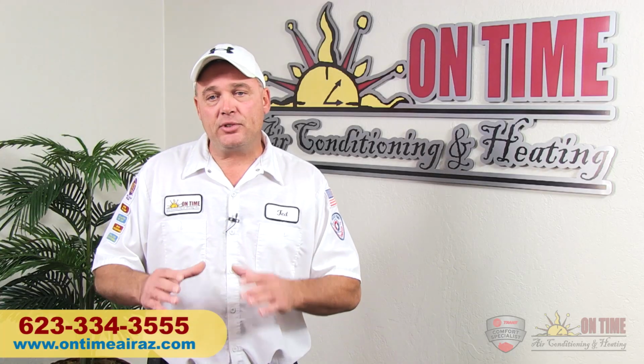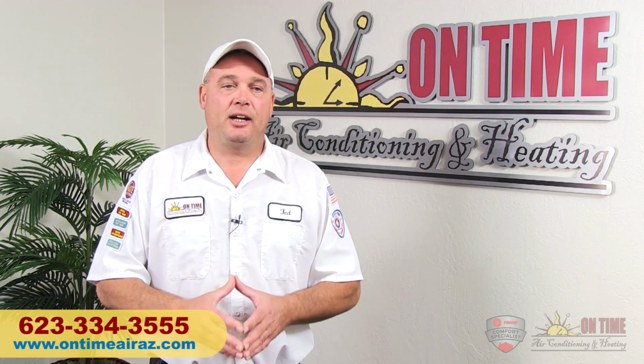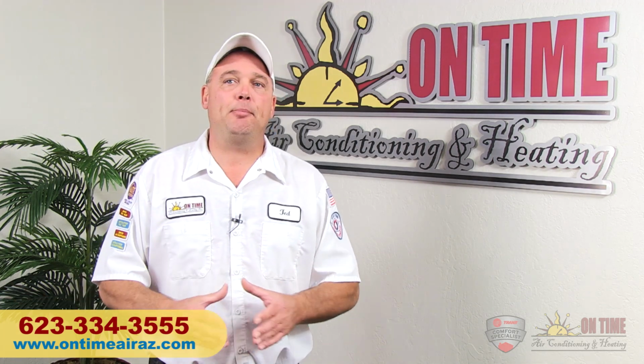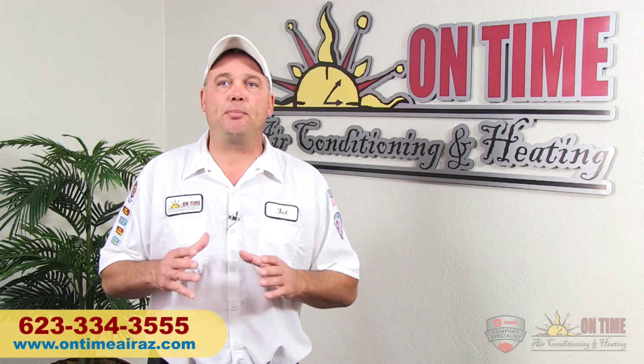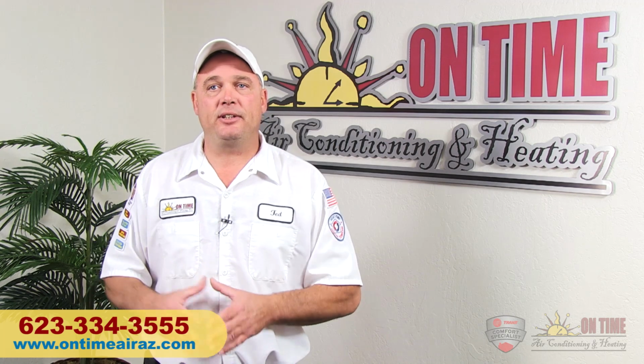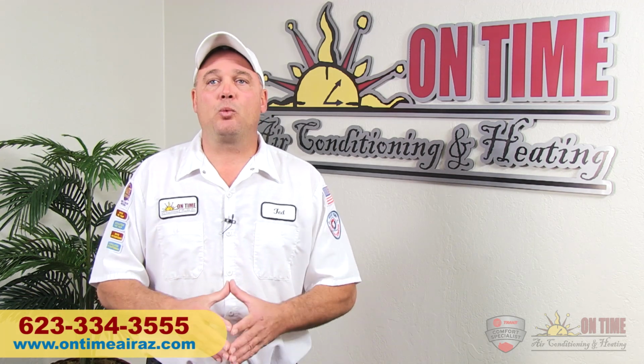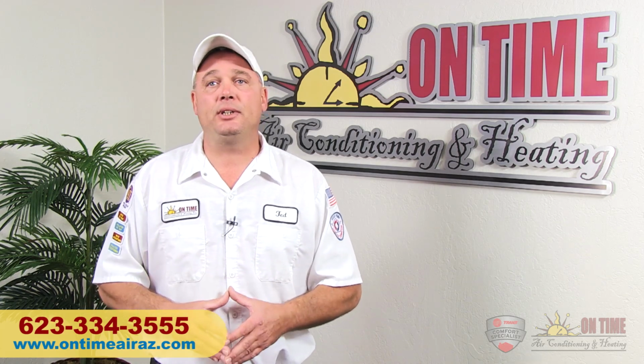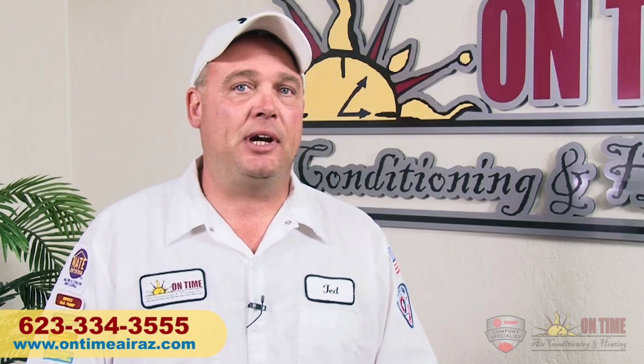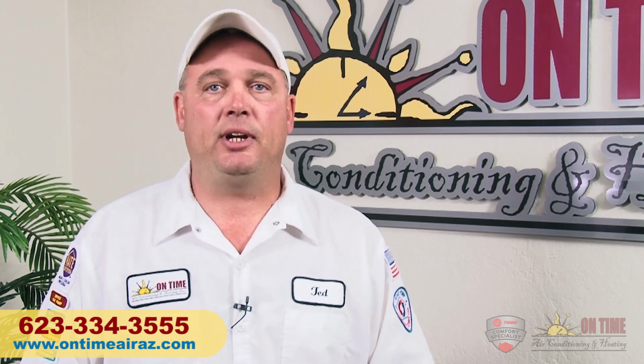So 75% of the time we come on in low gear. I dump my capacity by about 30%, so I'm only operating at about 70% of the power, 75% of the time. Because here in Phoenix, we size our units for worst case scenario. And we know here in Phoenix, even though we're 110 during the day, at nighttime we dip down to 80. Why do we need a big unit running when we're 80 degrees at night?